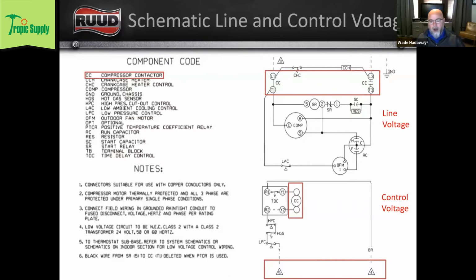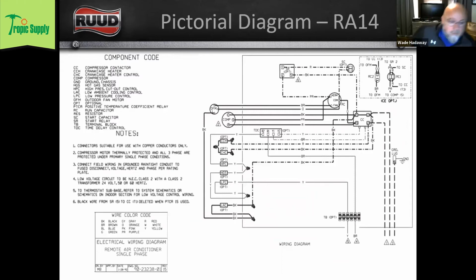Okay, and then here, Y and Brown are from our thermostat. Here's an example of a pictorial diagram, and on this pictorial diagram, you can see CC. That's still our contactor, and you can see that we've got L1, T1, L3, and T3. Off of our contactor, we've got a red wire coming off of T3 that goes to the run terminal on our compressor. We've got a black wire coming off of T1 that goes to common on our compressor. And then we have an orange wire that also comes off of T3 going to the common terminal on our dual capacitor.